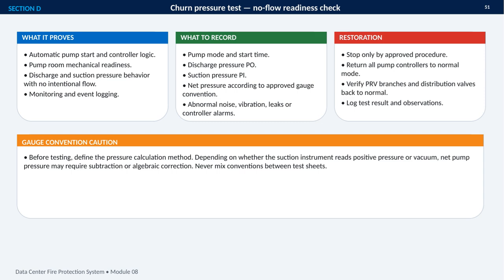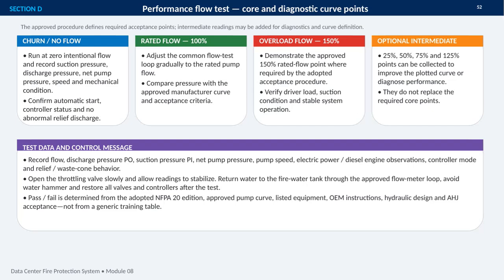This section defines the core and diagnostic points for a pump performance flow test. The approved procedure establishes the required acceptance points, while additional readings may help diagnose behavior and define the curve more clearly. At churn or zero intentional flow, I record suction and discharge pressure, net pump pressure, speed, and mechanical condition. I also confirm automatic start, controller status, and the absence of abnormal relief discharge.